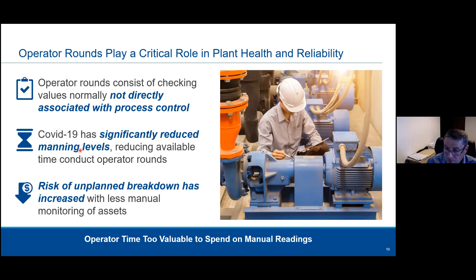You've also got the part where you're taking people out of the risk area. Putting operators in the field has been a necessity, but it puts people in harm's way. If we can reduce that - here's one of the simpler applications, a wireless pressure gauge. If you want the comfort of looking at a gauge to check the pressure looks about right, you've got that comfort factor. But that pressure gauge also sends a wireless signal to your historian, so you can start trending pressure measurements, not just 2 or 3 times a day - we can do that every minute, every hour, every couple of hours. We can bring that data in more regularly and consistently, especially with vibration measurement, taking readings from the same point every time, instead of relying on someone being good and methodical in their data collection routines. So a lot of advantages there.